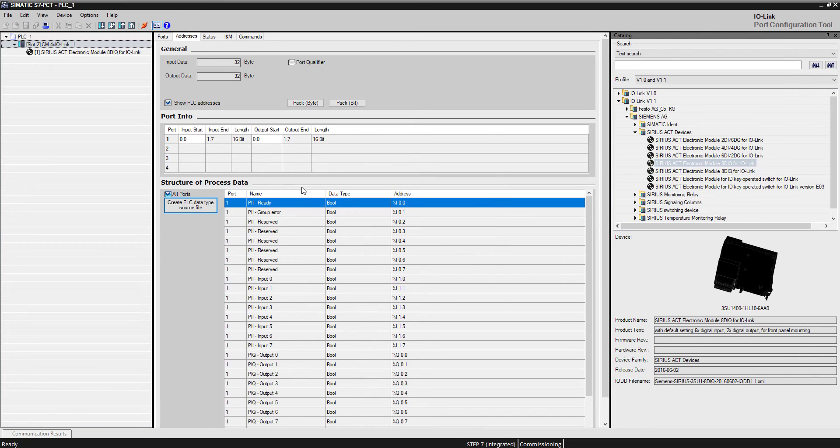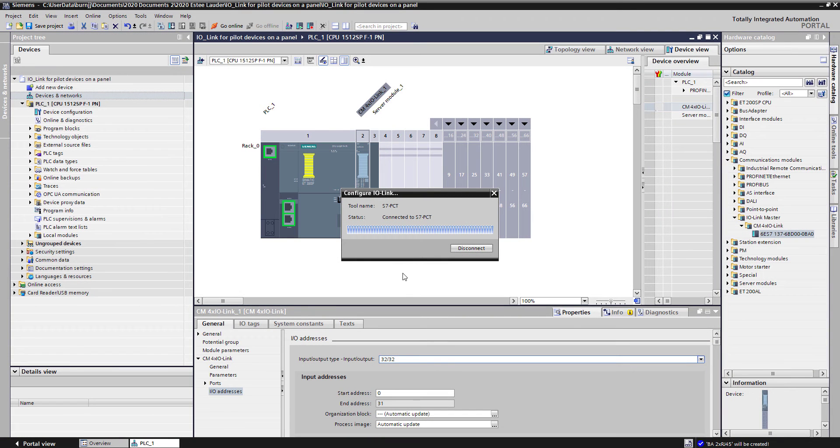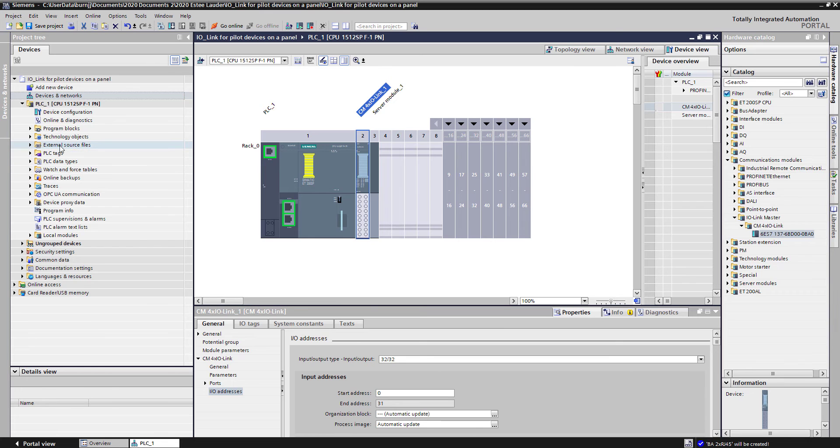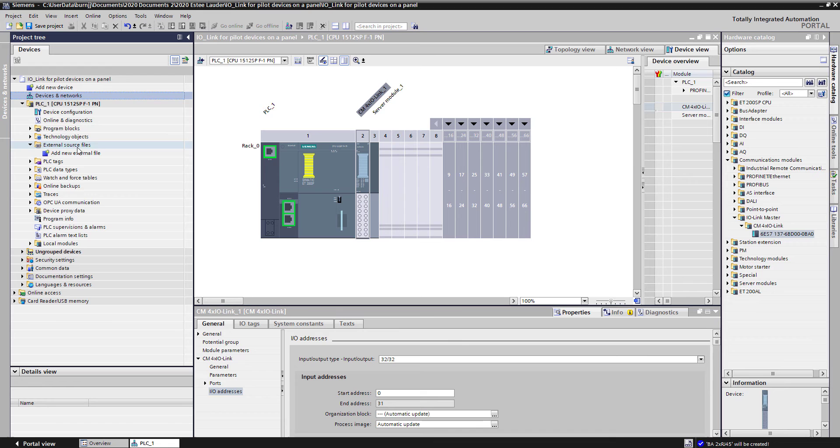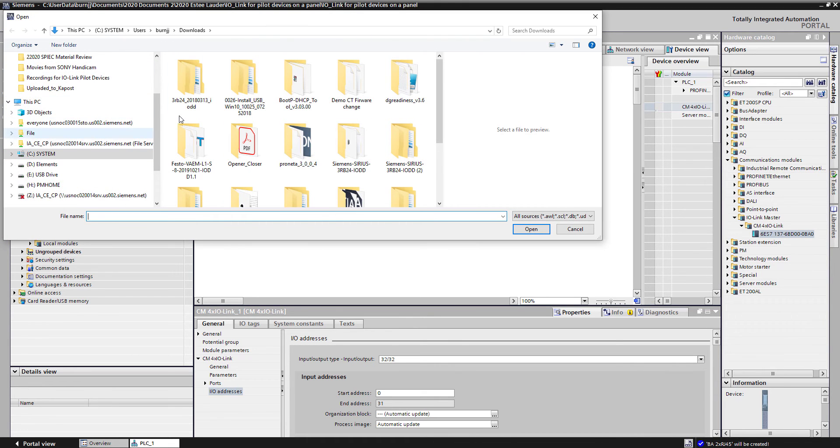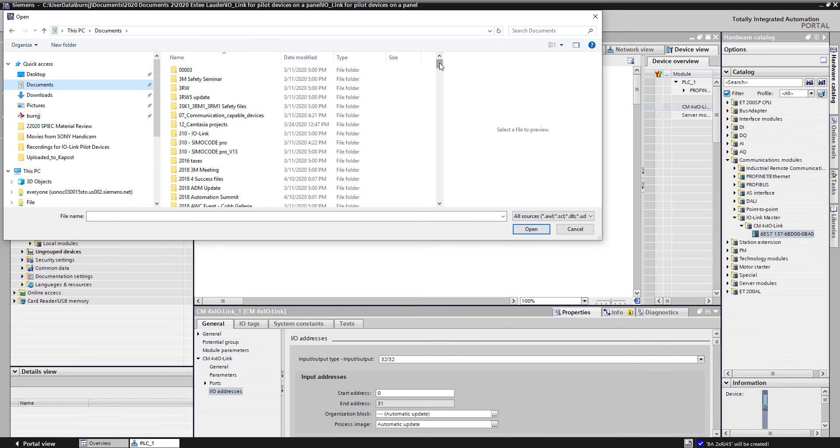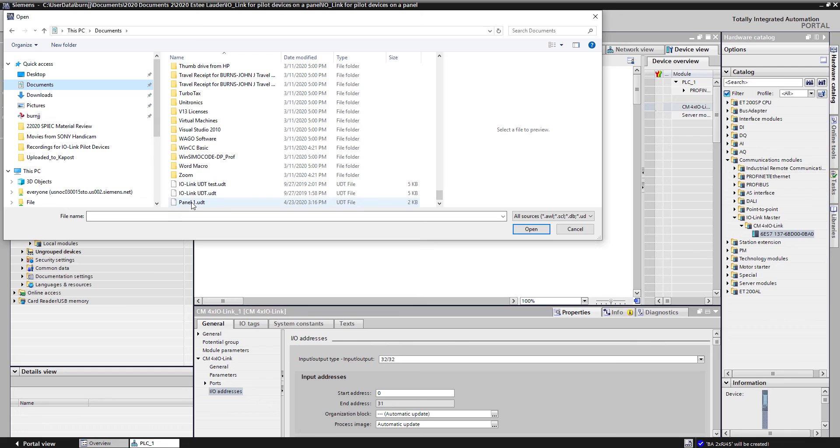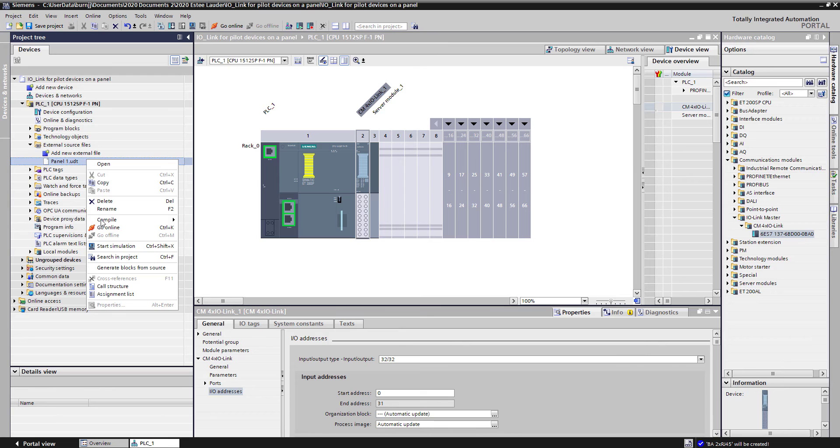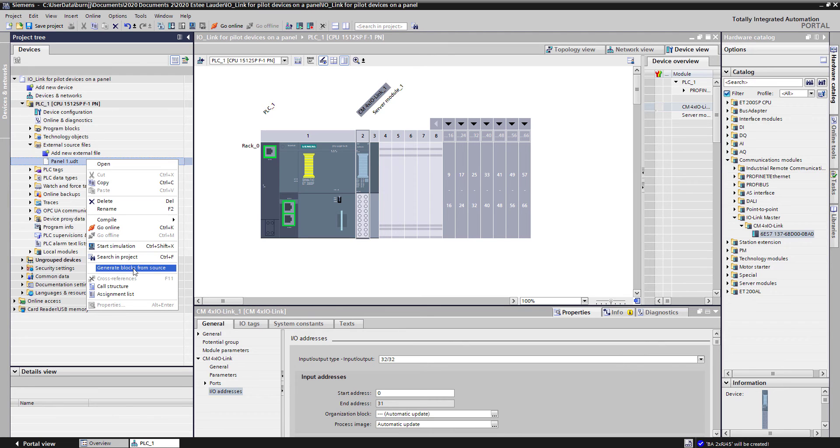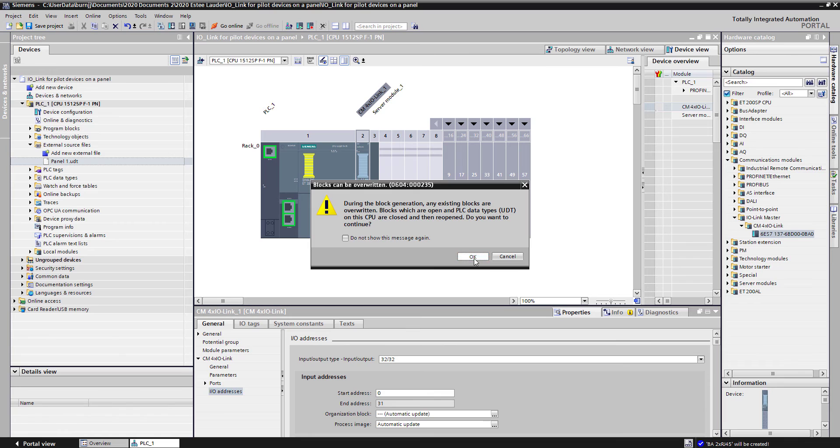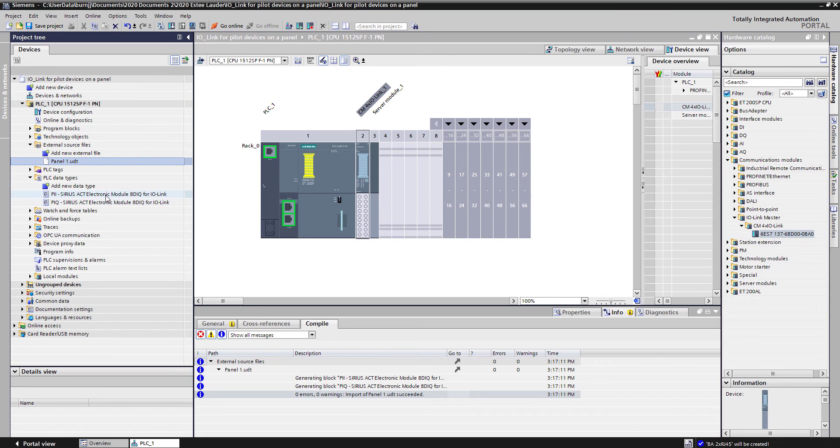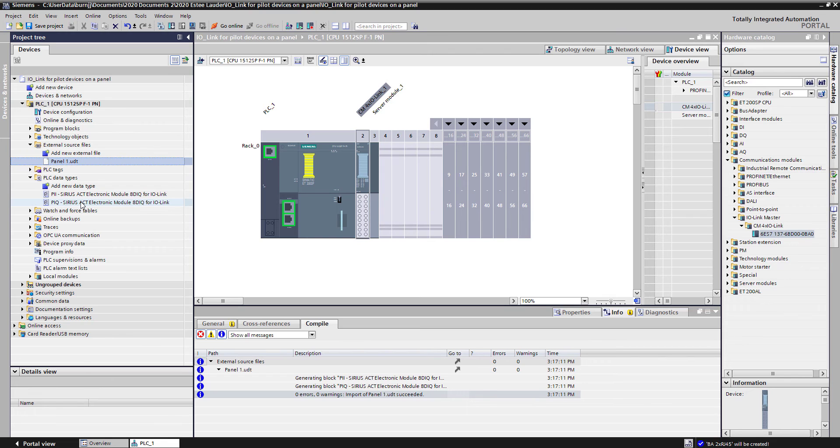Now I can exit out of the PCT tool. Now I want to bring that UDT file in to help assign tags for my program. The way I do that is if I come over here to external source files, I want to add a new external source file. We're going to go under my documents folder. If I scroll down, you'll see here's my panel 1 UDT. I'm going to open that up. Once I have that inserted, the next step is right-click and generate blocks from the source file. What that does now is it creates some data types forming for both the input image and the output image. And these are reusable data types.